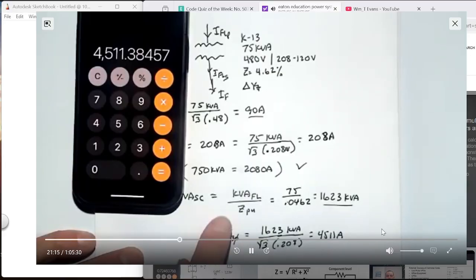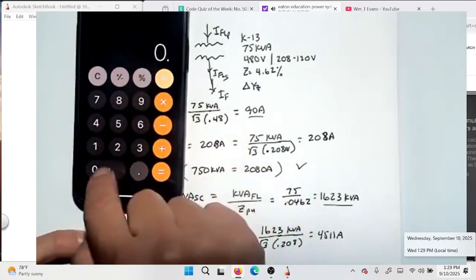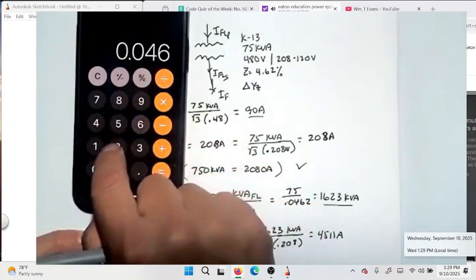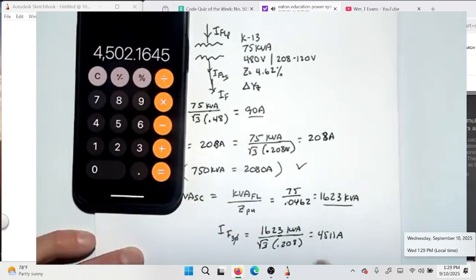If I took my number here that was 208 amps, I take 208, divide it by 0.0462, I end up with 4,502 amps, which is very close to that number. I was just off by basically the square root of 3 factor that works out in there.